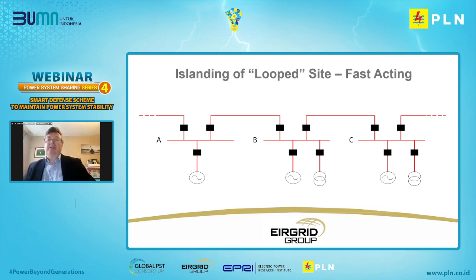So here, again, we're showing 3 two-line stations in a row, stations A, B, and C. And here we're showing an example of fast-acting islanding. So the 2 lines into station B are going to trip, islanding station B. So if you can advance one, next slide. Okay, so the breaker has opened at station B, and that's going to slave trip its partner breaker at station B. Now, station B is still connected. So now the line to station C is going to trip.